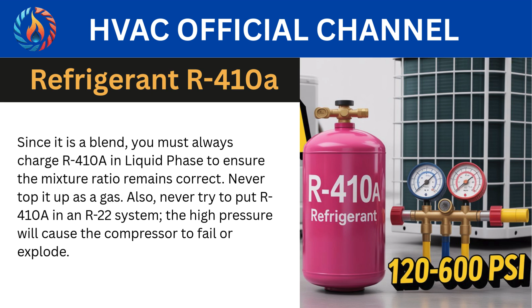Also, never try to put R-410A in an R-22 system. The high pressure will cause the compressor to fail or explode. So friends, this was complete information about refrigerant R-410A.